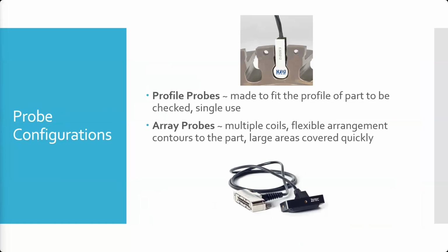Something like this could have a coil on each side, or it could have a coil on one side where you'd have to run it through one way, flip it around, and run it through the other way to check the other side. Or it could have a coil that follows the profile, some kind of odd shaped coil. There are all different ways they can run the wires inside of there where it'll induce the field.